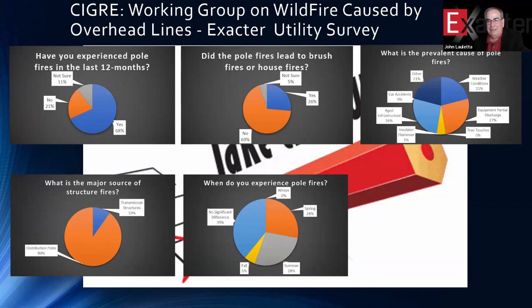We asked the participants, when do you have pole fire problems? And I can tell you from our customer standpoint, they tell us the spring is the worst time where most fires are prevalent. It follows, of course, the winter salting of roads and a lot of contamination issues. But in the survey, it was pretty much split between summer and spring. And then a big portion said they didn't see any correlation to the time of year. It just, they pop up.